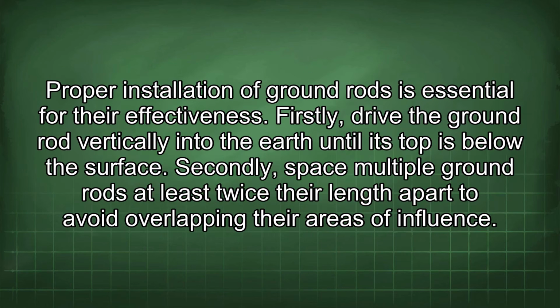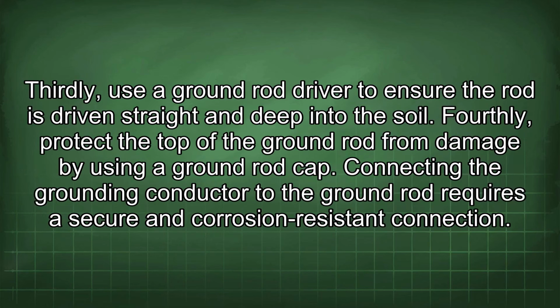Proper installation of ground rods is essential for their effectiveness. Firstly, drive the ground rod vertically into the earth until its top is below the surface. Secondly, space multiple ground rods at least twice their length apart to avoid overlapping their areas of influence. Thirdly, use a ground rod driver to ensure the rod is driven straight and deep into the soil. Fourthly, protect the top of the ground rod from damage by using a ground rod cap.